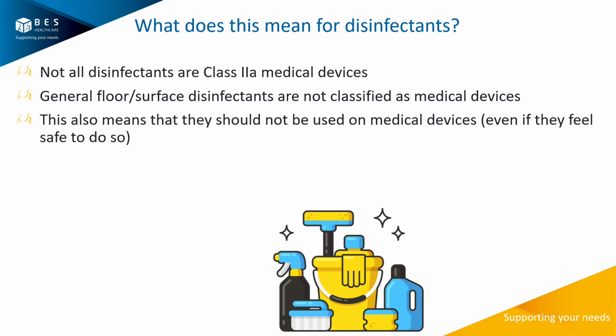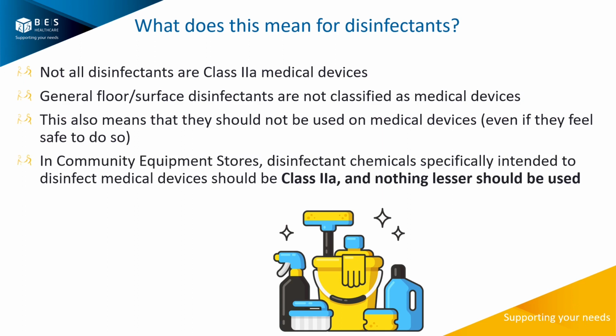They actually haven't gone through the accreditation and safety processes to make sure that they are safe for use in that way. So in all community equipment stores, all loan stores, disinfectant chemicals need to be used on the right type of devices. So if you're using a disinfectant on medical devices, and most of what you reprocess is medical devices, then it needs to be Class 2A and nothing less.